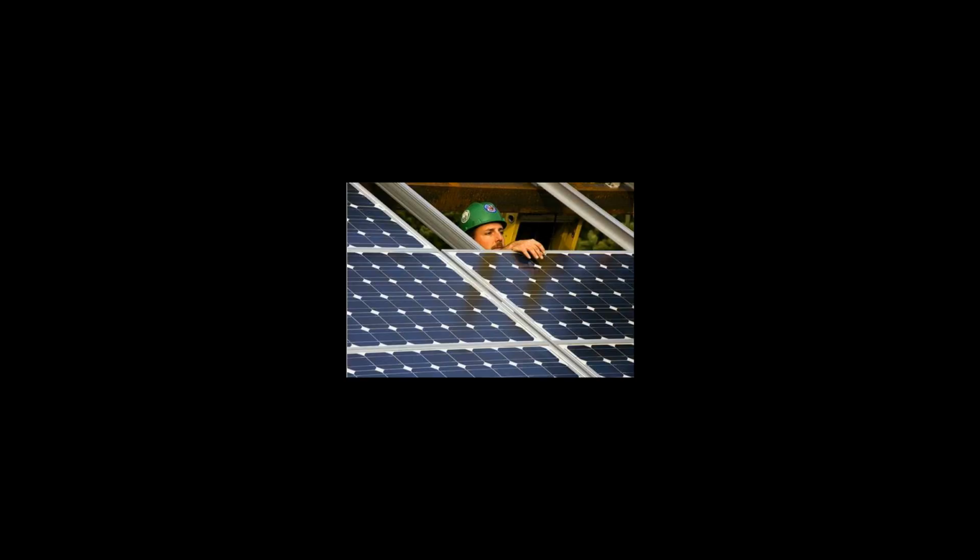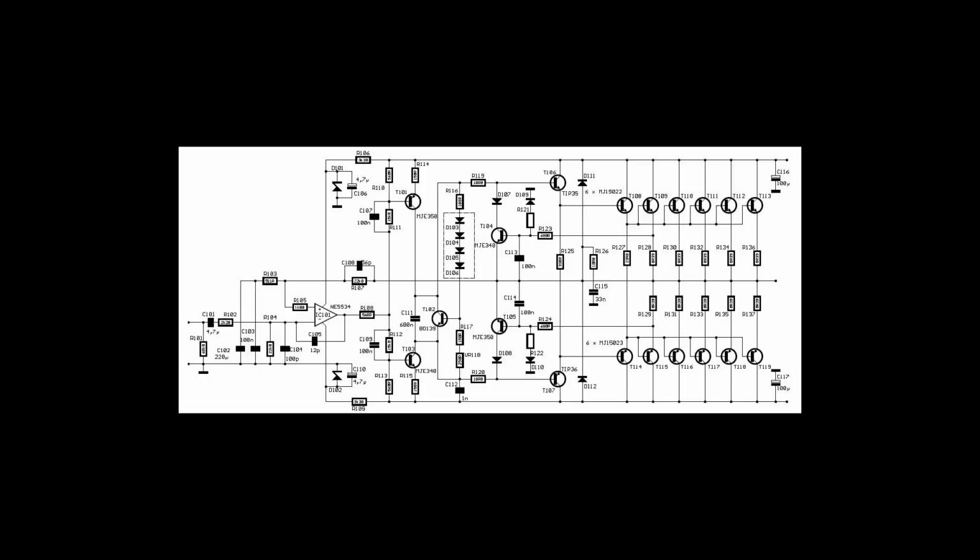A smart module is a power optimizer integrated into a solar module. A microinverter essentially combines a power optimizer with a small inverter in a single case that is used on every panel, while the power optimizer leaves the inverter in a separate box and uses only one inverter for the entire array. The claimed advantage to this hybrid approach is lower overall system costs, avoiding the distribution of electronics.